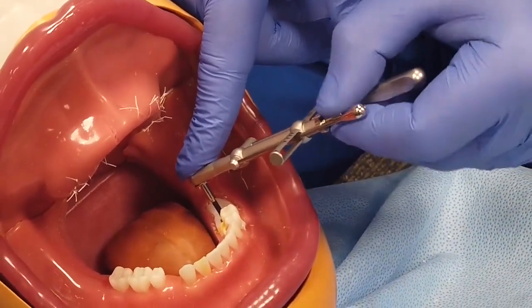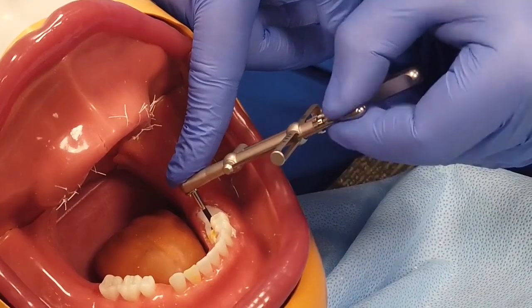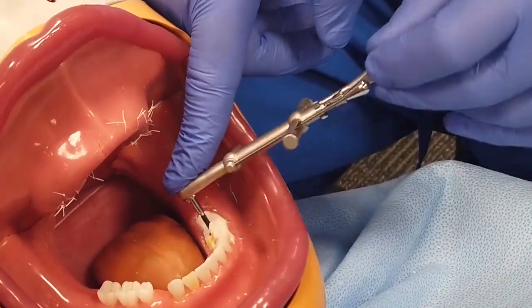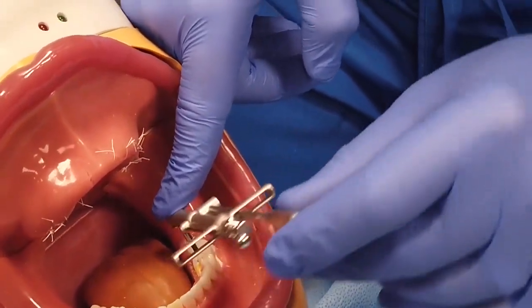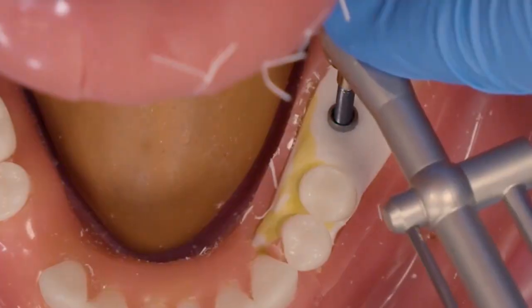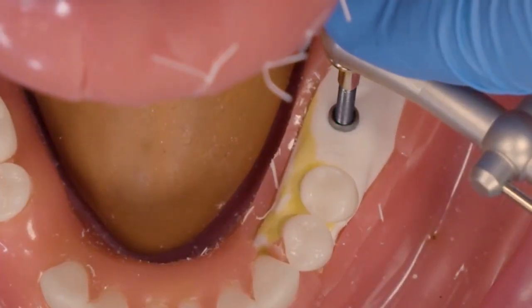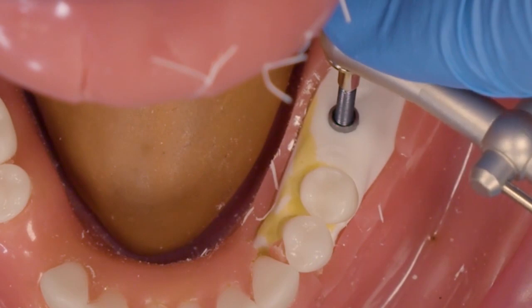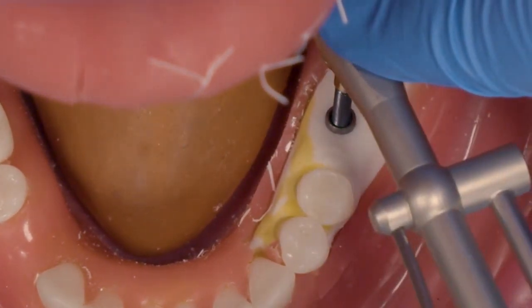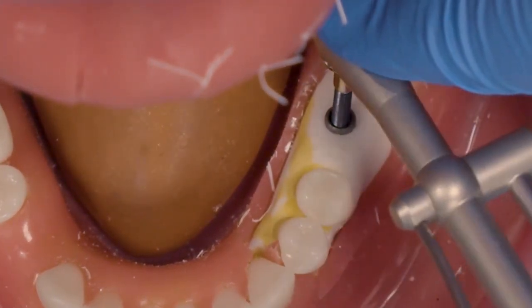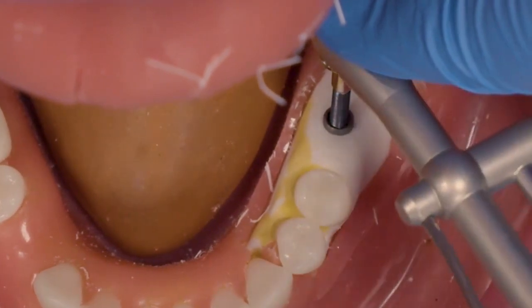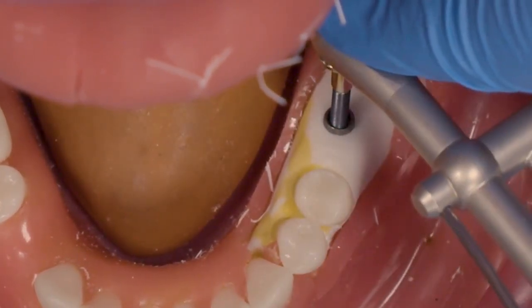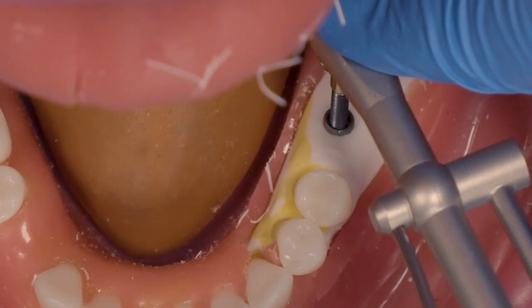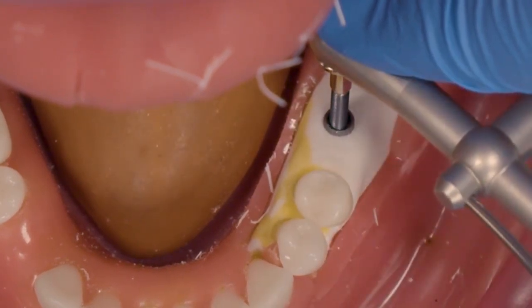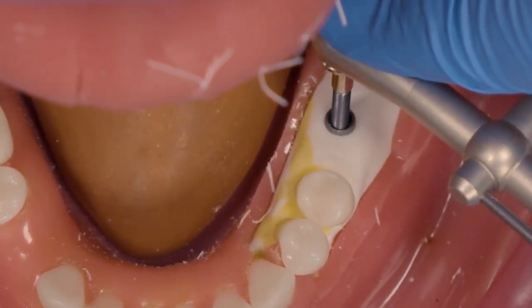And the way this implant removal kit works, it's reverse engineering. So if we're going to tighten this screw, it's going to go clockwise. As we tighten this screw, you will start feeling the resistance. And the recommended torque, as you see on the torque wrench, we want to torque that screw to about 60. So as you tighten it, now it's skipping when it gets to about 60.